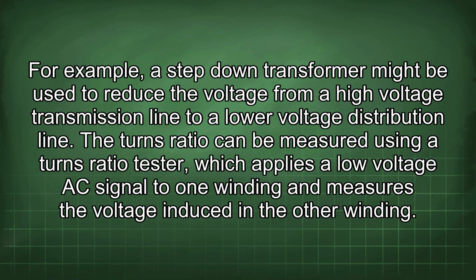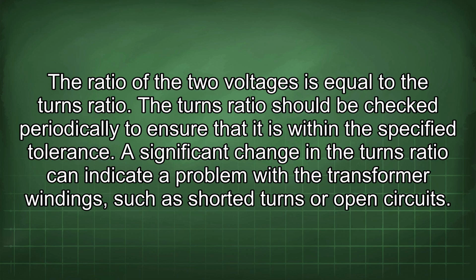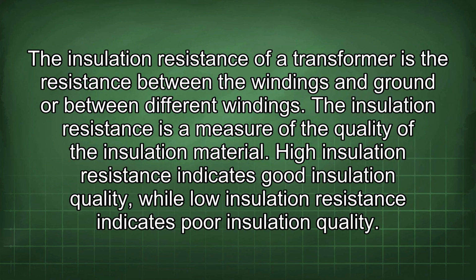distribution line. The turns ratio can be measured using a turns ratio tester, which applies a low-voltage AC signal to one winding and measures the voltage induced in the other winding. The ratio of the two voltages is equal to the turns ratio. The turns ratio should be checked periodically to ensure that it is within the specified tolerance. A significant change in the turns ratio can indicate a problem with the transformer windings, such as shorted turns or open circuits. The insulation resistance of a transformer is the resistance between the windings and ground or between different windings.